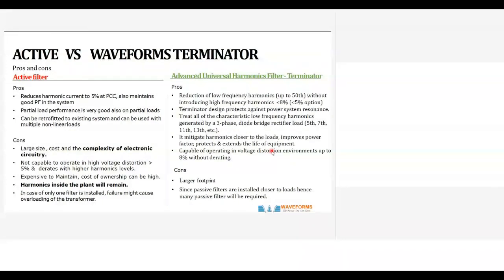The disadvantages are large size, cost, and complexity. Installation is complex. You'll have to install CTs and all that, provide air conditioning, and if it is dusty, you'll have to keep the place clean. The electronic circuits are costly and complex. If there is high voltage distortion, the operation can be a problem. It is expensive to maintain, the cost of ownership can be high. So the harmonics inside the plant will remain. This is an important thing.